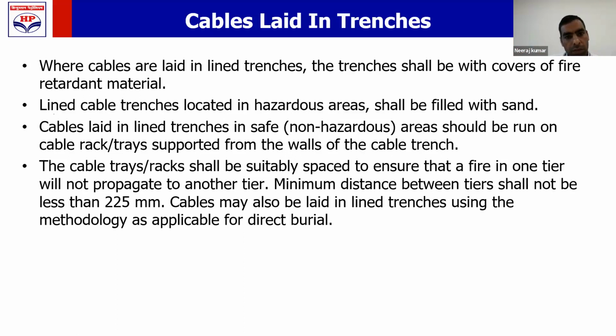If your cable trench is inside a hazardous area, then you should fill it with sand. If it is in a safe area, then the sand filling requirement is not there. You can simply make a trench, cover it with the cable checkered plate or cover it with fire retardant material like slabs, and you need not fill the sand in that trench. Ensure that that area is a non-hazardous safe area. In that case, the requirement of putting bricks is not there.